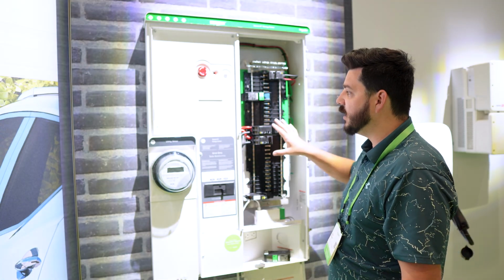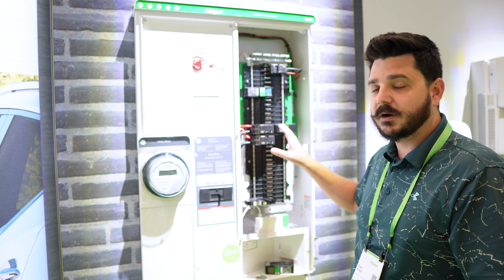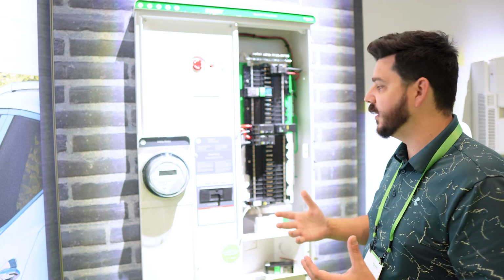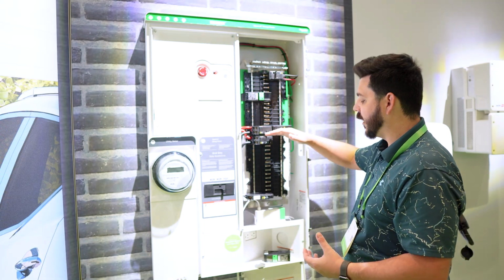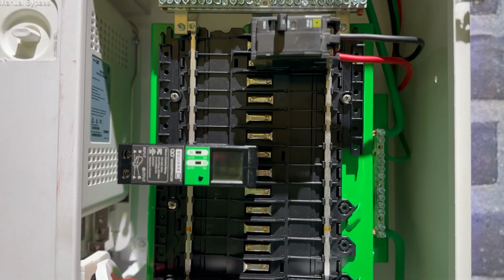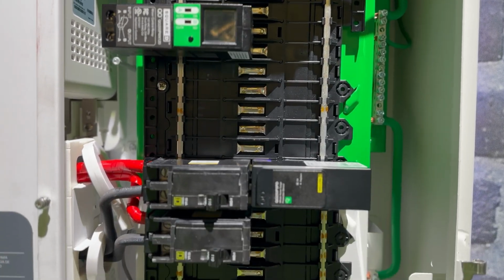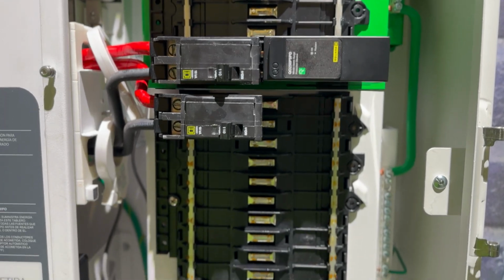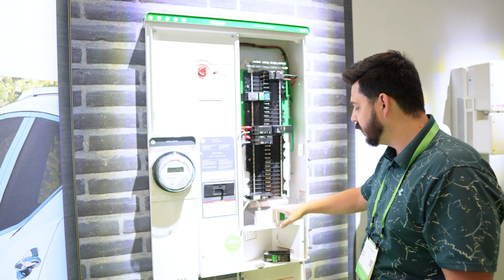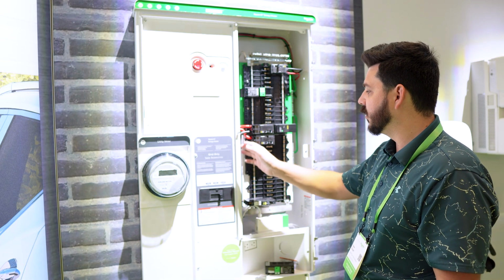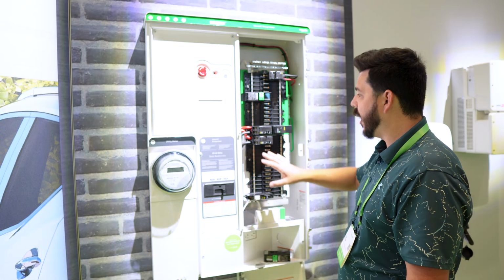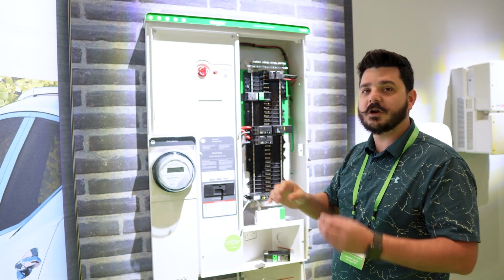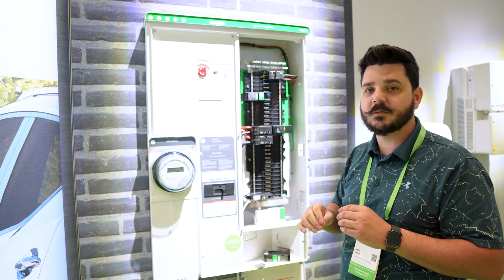What's really unique about this product that Square D was able to develop and integrate is this split bus bar design. The top half is the emergency loads panel, and the bottom half is the non-essential loads panel. Square D has included the Wiser, which can monitor the consumption of all the loads and help identify them, so you know exactly how much energy they're consuming individually.